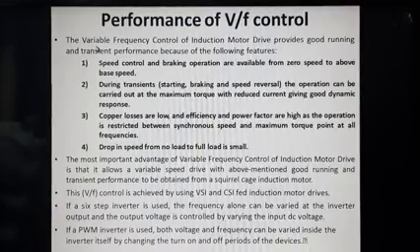So the magnetizing current magnitude will get reduced compared with simple frequency control, because in the saturation region, for bringing a small change in the value of flux, you have to increase the magnetizing current to a large value. So in the V by F method of speed control, the motor does not move to the saturation region. It is retained in the knee point region itself.